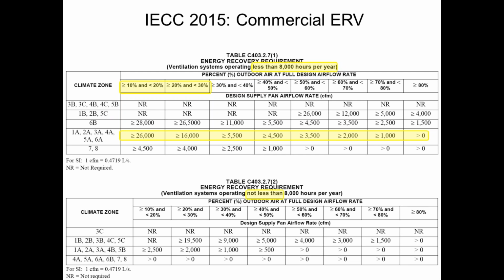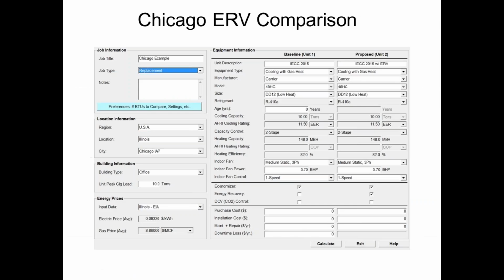The other thing that's new is the entire table on the bottom. They added a whole new table on here, and if you look at that, all sizes for climate zone 5A, doesn't matter how big my rooftop is, if I'm bringing in more than 10% outside air, I'm required to have an ERV if my system operates more than 8,000 hours per year, right? So there's like 8,760 hours in the year. So essentially, if I have a 24/7 occupancy project, I'm going to need to put an ERV on there unless one of those prior pages of exceptions applied to me.